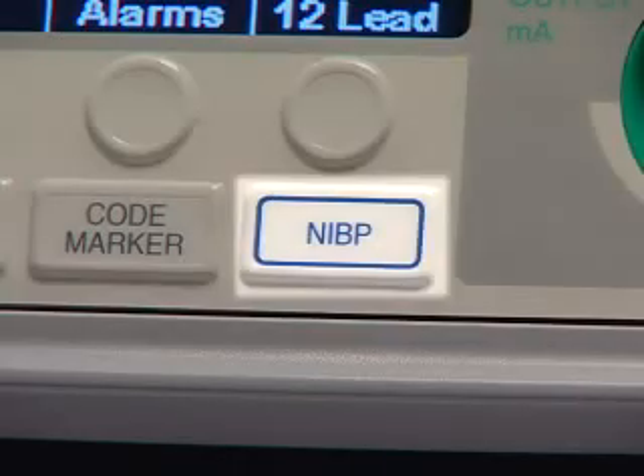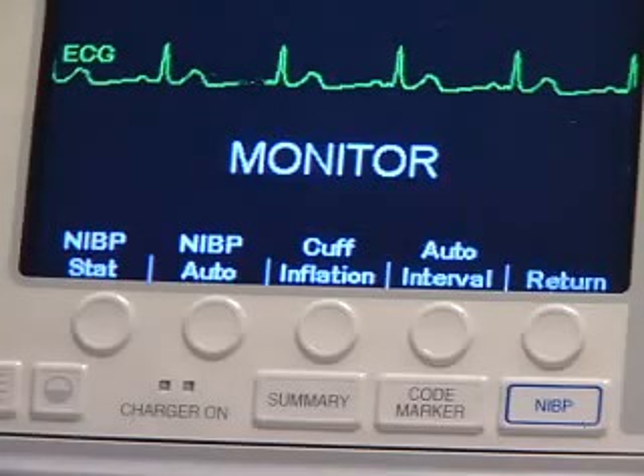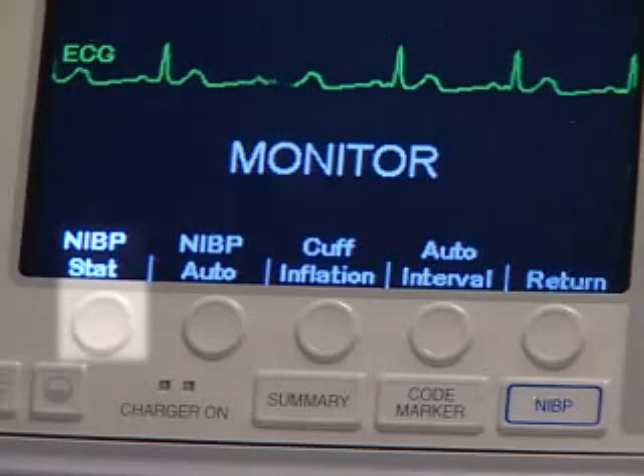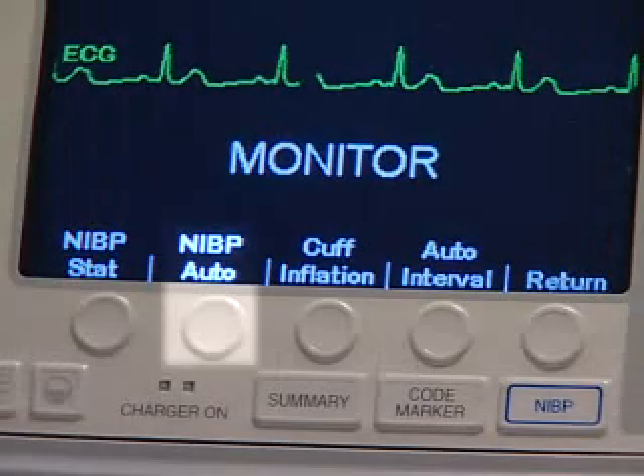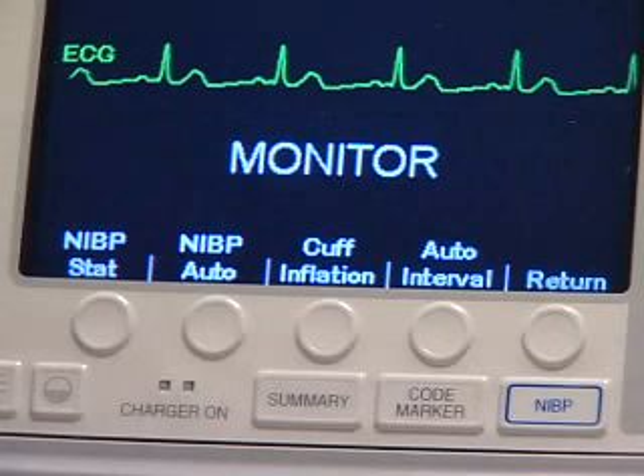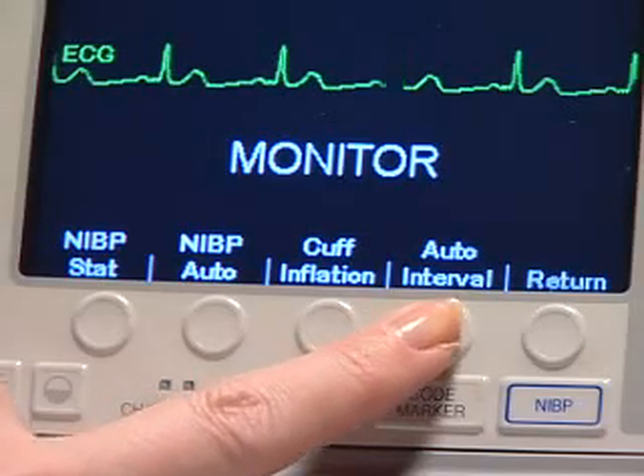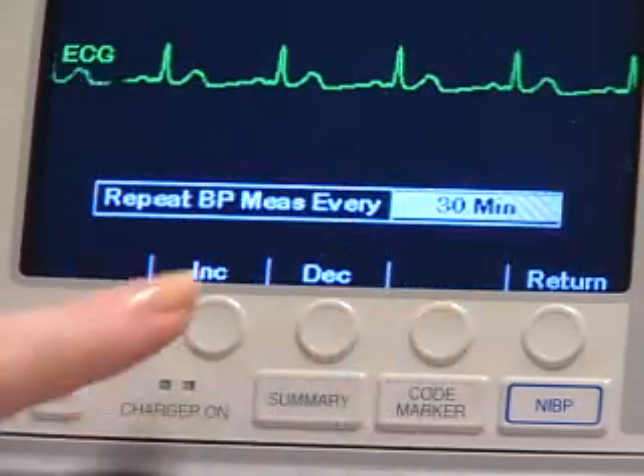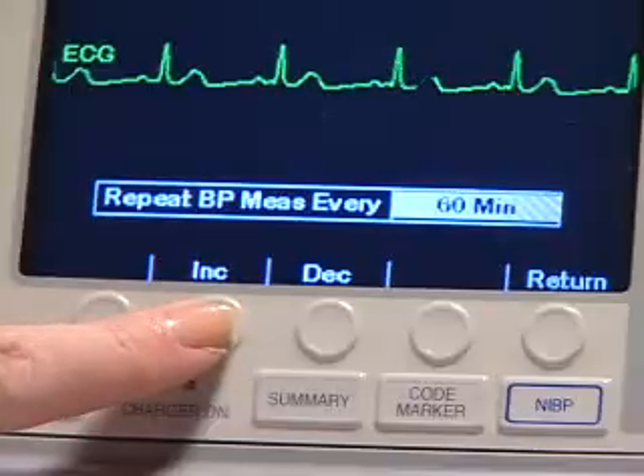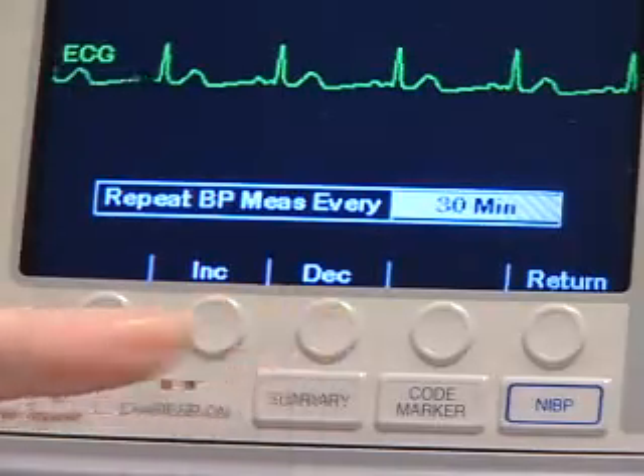The front panel NIBP button can be configured to start in either Auto or Stat mode. NIBP Stat allows you to take up to 10 BP readings within a 5-minute period. NIBP Auto allows you to take automatic NIBP measurements at preset intervals. These intervals can be set between 2.5 and 120 minutes. The settings can be easily changed by pressing the Auto Interval soft key and pressing the Increase or Decrease soft keys to adjust the settings.